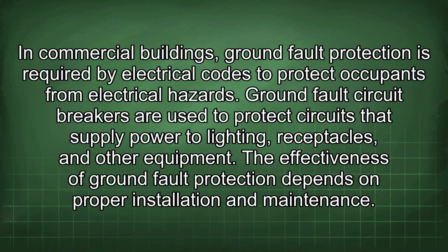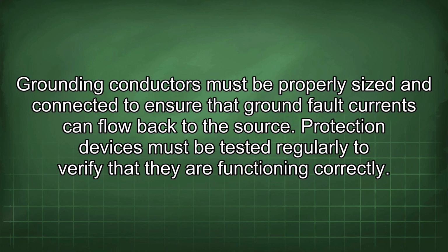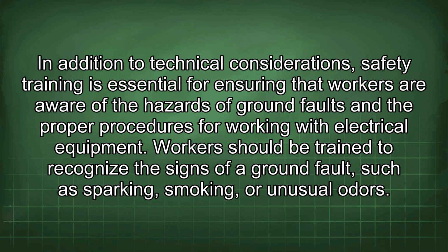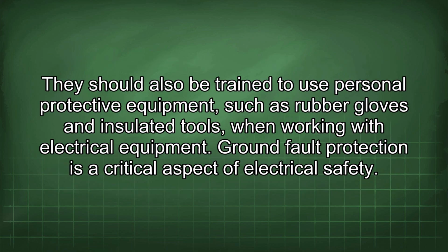The effectiveness of ground fault protection depends on proper installation and maintenance. Grounding conductors must be properly sized and connected to ensure that ground fault currents can flow back to the source. Protection devices must be tested regularly to verify that they are functioning correctly. In addition to technical considerations, safety training is essential for ensuring that workers are aware of the hazards of ground faults and the proper procedures for working with electrical equipment. Workers should be trained to recognize the signs of a ground fault, such as sparking, smoking, or unusual odors. They should also be trained to use personal protective equipment, such as rubber gloves and insulated tools, when working with electrical equipment. Ground fault protection is a critical aspect of electrical safety.